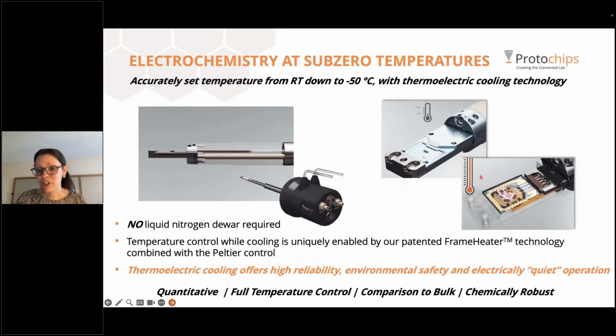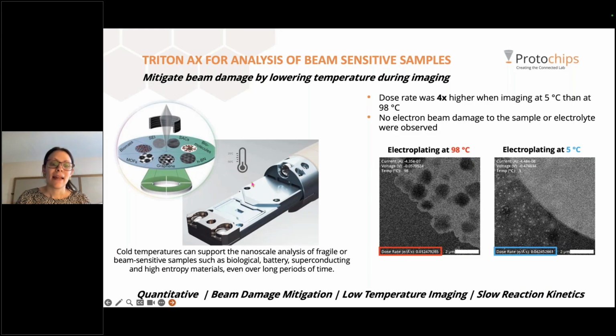So to modulate the temperature, you'll run the Peltier device, so the cooling will take place, and then simultaneous to that, the heating coil, the frame heater technology I was talking about earlier, will compensate and help modulate the temperature if you're trying to go to minus 25 or minus 30 or 0 degrees, somewhere in between that range. The two will work together to heat from the cooled temperature and help you modulate in the middle of your experiment to whichever temperature you would like. And so that's the operation of the Triton system itself.